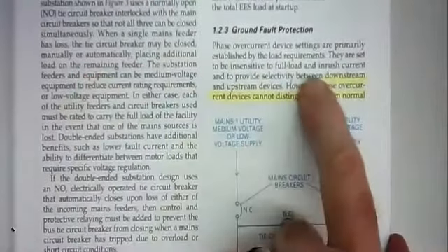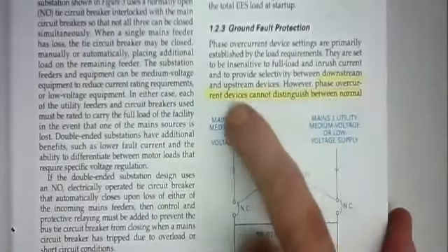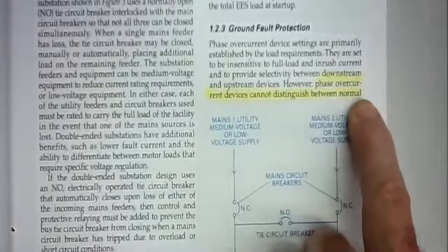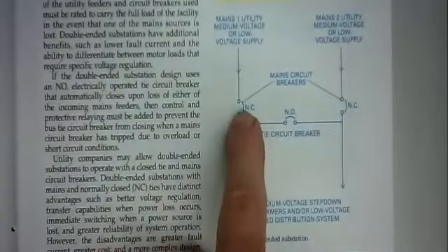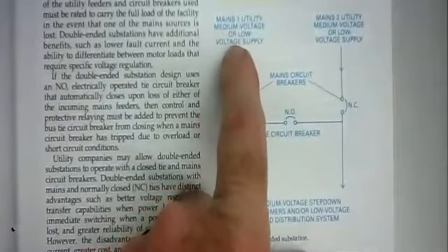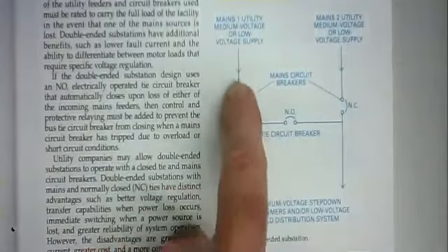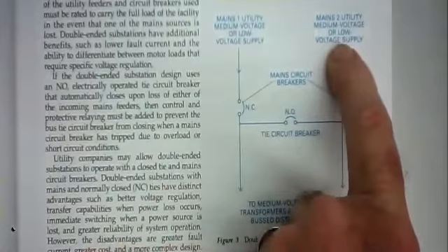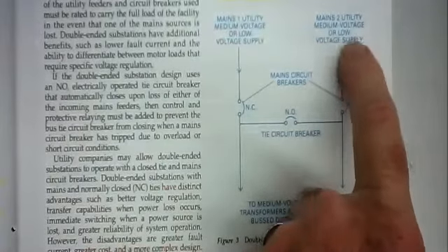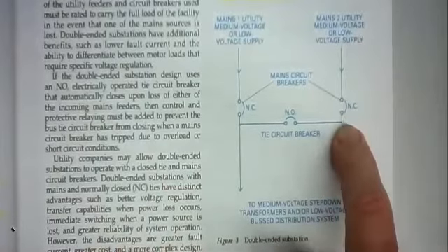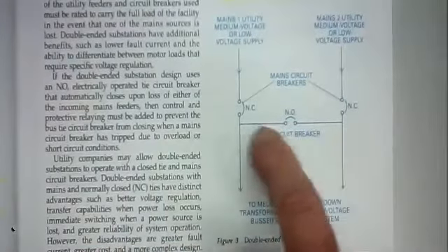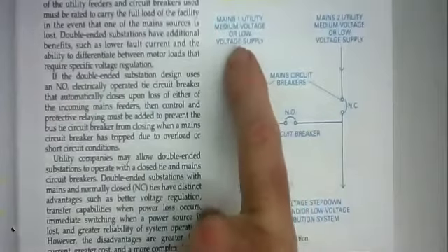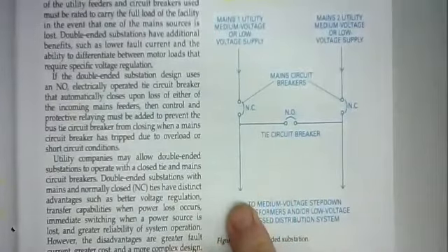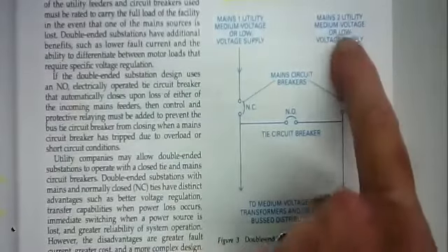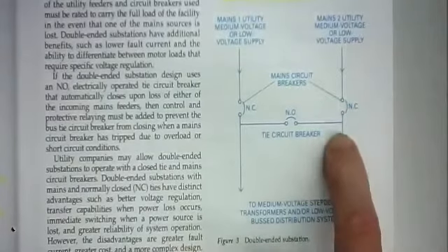Well, ground fault protection, it says downstream and upstream devices. However, phase overcurrent devices cannot distinguish between normal overcurrents and ground faults. But now let's take a look at this spot network. You have a substation from the utility in a neighborhood, and it's coming into the hospital on one service. There's a whole other substation in a different neighborhood, a different city block, that comes to another service disconnect in that same hospital, and there's a tiebreaker between them. At any time, you can have one main from the utility serving some of the loads, or you can have the other main from the other substation serving those same loads or different loads.